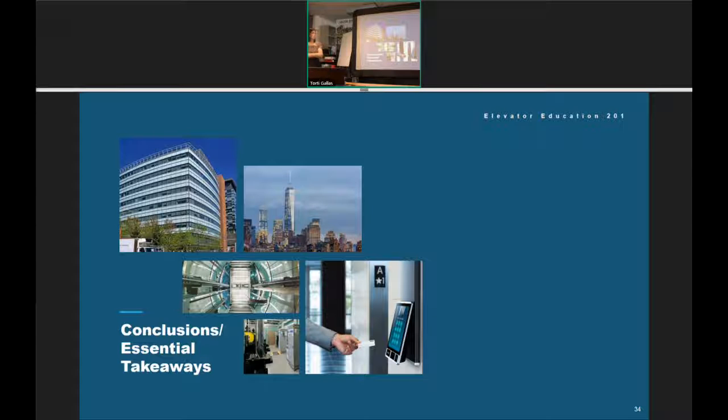But I know with some of the machine roomless units that are truly machine roomless, where the controller's in the jamb and the elevator companies are providing the disconnect, you still need to have the power from the hoistway back to the control space or to where the main line switch is. You're going to have to have a disconnect there, so that's fine. But as far as trying to group it all with an IT controller space, with the actual elevator, most of the time, probably 99.9%, you're going to need your own dedicated space.